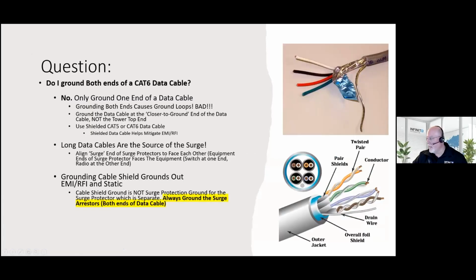And this is just showing that data cable, and this is a great question, because a lot of people ask about it: do I ground both ends of the shield on that data cable? And the answer is no, because when you do that, you could cause a ground loop scenario. So, well, which end do I ground? Water runs downhill, like electrons, right? So you want to ground the end of the data cable closer to the ground, not at the tower top. So that's really basically simple.